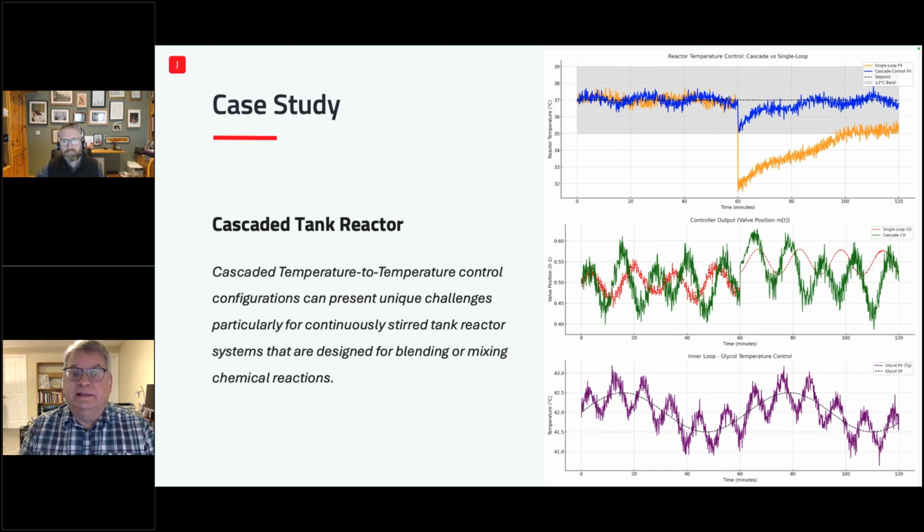Well, in this case, yeah, it's a good batch versus a bad batch, if you will. Now I've got to involve quality, and we've got to go find out if we've ruined the proteins, and many ELISA tests later, we find out the result. That's a lot of money. So we implemented cascade control to take care of that problem. And the cascade is simply the thermolator is just detecting temperature upstream of the reactor, and we're just offsetting that and circulating more. It's a lower temperature fluid that's coming through there, but we're doing more of it to continue the delta T in the reactor.